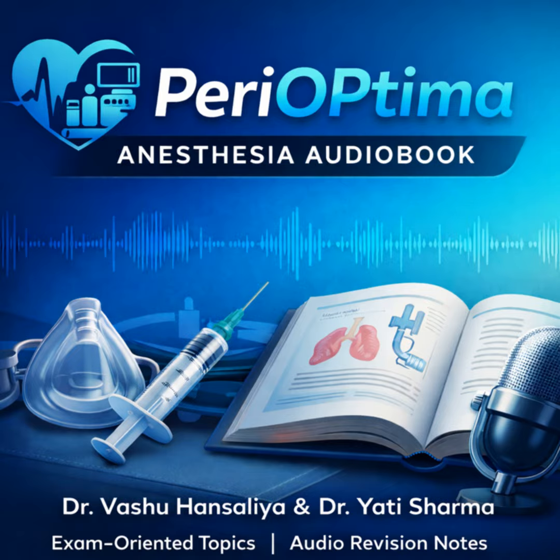So focusing on its utility, what are the primary clinical situations where the Bain is preferred? Because it's lightweight, flexible, and has long tubing, it's highly suitable for remote location anesthesia. So think head and neck surgery, ENT, ophthalmology, where the patient's head is draped and the anesthetist needs to be positioned away from the surgical field. And for transport. Excellent for transport. Moving a ventilated patient over short distances is much easier with a Bain than a full circle system.